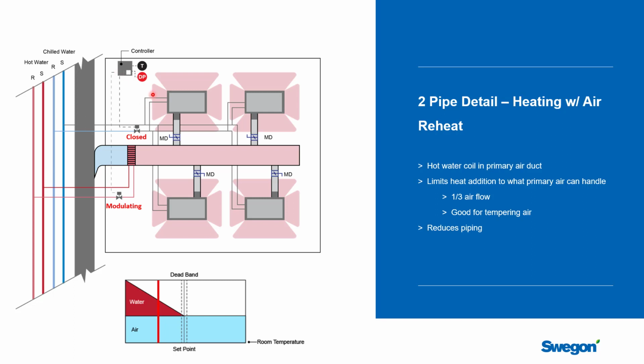the controller, if it sees the temperature drop, as we see here, we've moved below the deadband, it can modulate that valve to put heat in. Do remember that only about 1/3 of all the air that's moving through this room is the primary air. The other 2/3 is the room air that's passing through these coils, and you're only putting the heat into this primary air. So there's a limit to how many BTUs you could actually introduce into here without getting some fairly high air temperatures in this primary air, and how well the beams would work, and possible issues of stratification. You'll get the heat into this control zone, but you might find that the air doesn't distribute as well as you want. But for a little bit of reheat, this is a very viable solution.